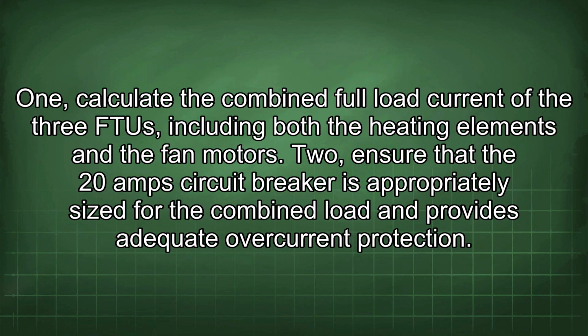1. Calculate the combined full load current of the three FTU, including both the heating elements and the fan motors. 2. Ensure that the 20 amp circuit breaker is appropriately sized for the combined load and provides adequate overcurrent protection.